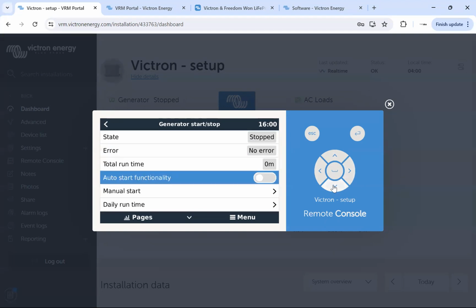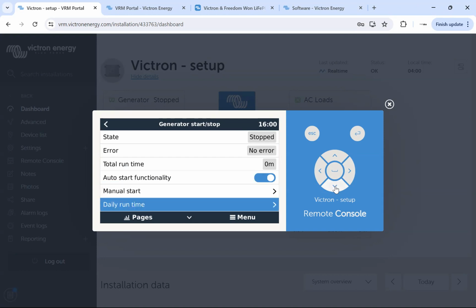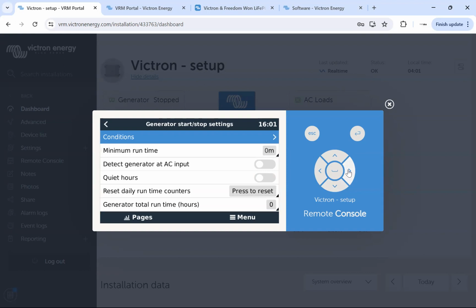functionality. So we can now go, I want this to be an automatic start stop generator, and you basically need to order a generator that is 2-wire auto start. So it needs a 2-wire auto start input on the generator for this functionality to operate properly. And then you run from normally open and common of the relay on the GX device straight to the 2-wire auto start on the generator. And then you set it up like this. Settings.